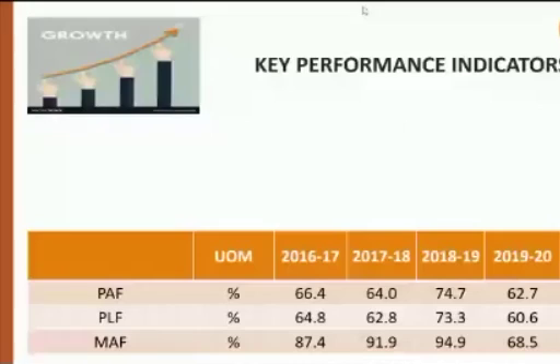Meanwhile, I would like to share that we are very much concerned to improve our heat rate. For that, we do online water wash periodically, every two or three days, as well as offline water wash of the machines at an interval of three to four months, or whenever we get the opportunity to do the offline water wash. With this, we could achieve a heat rate near to the design heat rate of the machine.